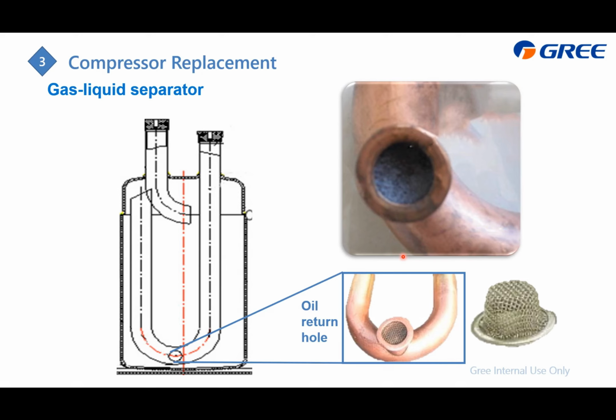And it will generate lots of impurities. And we're just afraid that the impurities will block this filter, and sooner or later the oil will always accumulate at this gas liquid separator, which will lead to not enough oil for the compressor operation, and sooner or later the compressor will run out of oil and lead to another breakdown again. And this is the reason why we require replacing the gas liquid separator.